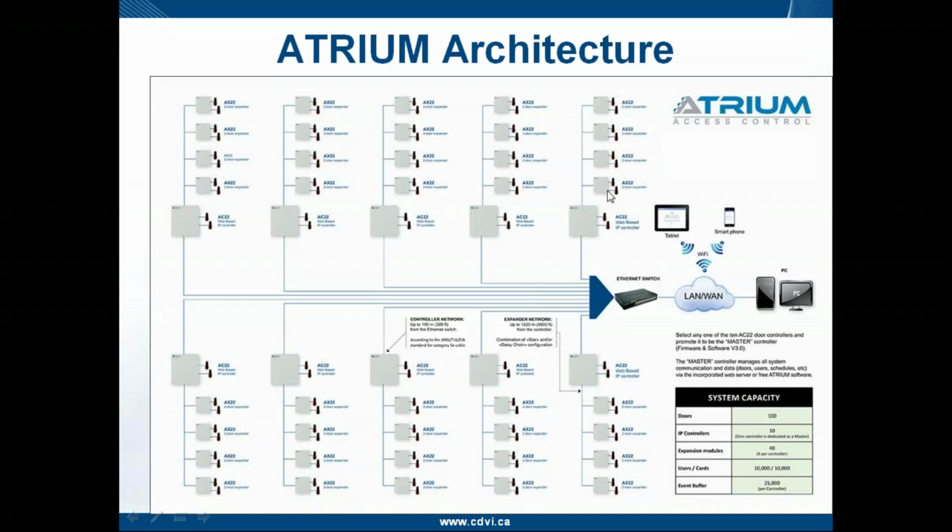So if the expander goes offline, we now know how the expander will react. The doors will lock. The last 500 cards of each reader will work for 7 days. In addition, of course, in the system, you'll have an event, module communication failure. This can be flagged to fire an email and so on and so forth. And the 2 readers on that expander at the door will start beeping, chirping, I should say, every 3 seconds, along with a red LED flash. This is a visual and audible indicator that there's something not normal at this particular door.